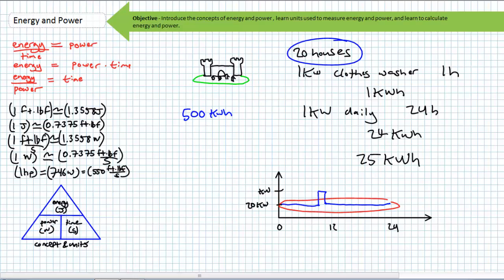However, in the worst case scenario, where every single one of your 20 houses takes their alpha particle laden workwear and shoves it into the washer and presses start simultaneously, you're going to get a 20 kilowatt peak load. This means you've got to purchase, at a minimum, a 20 kilowatt generator.